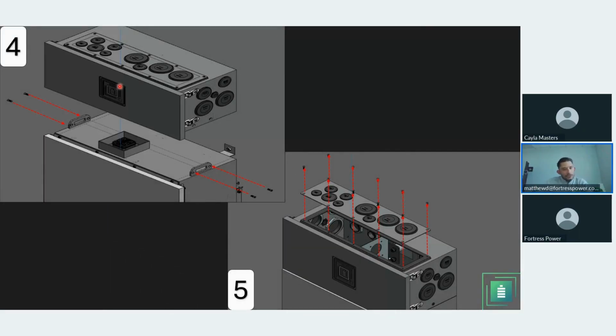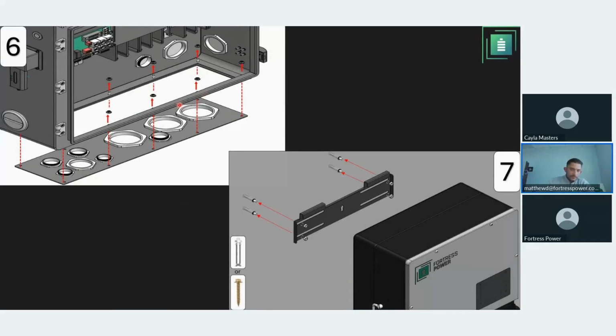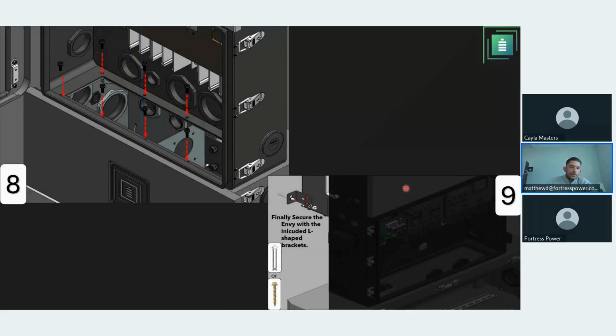Stack the E-way on top of the eBoost, and then secure it with these 4 bolts on the side, and then remove the top cover to encompass the Envy. Remove the bottom cover of the Envy. Install the wall mounting bracket, and then install the Envy on top of the wall mounting bracket, and then secure the bolts on top of the E-way. So secure the Envy with the E-way in order to create that nice seal for outdoor applications. And then finally secure the L-shaped brackets from the Envy to the wall. Pretty simple.